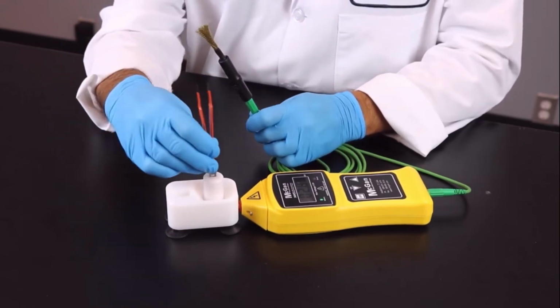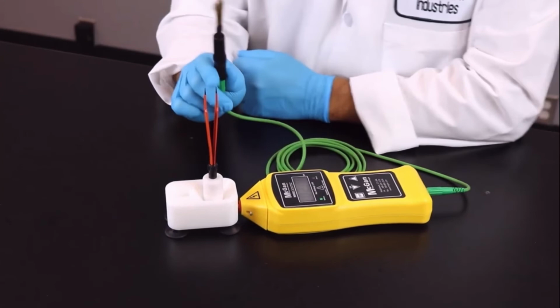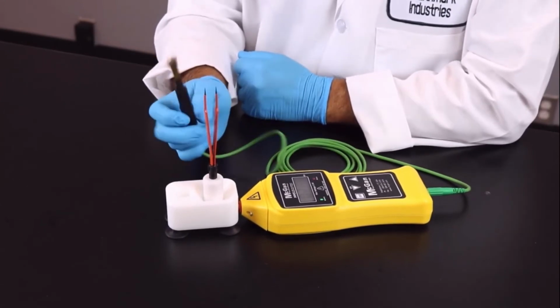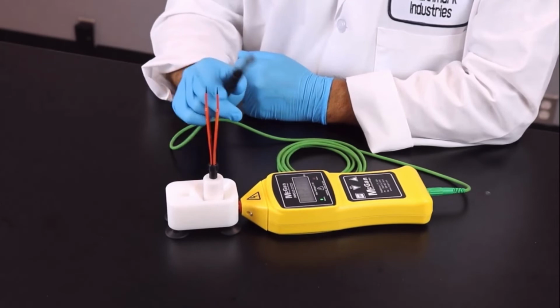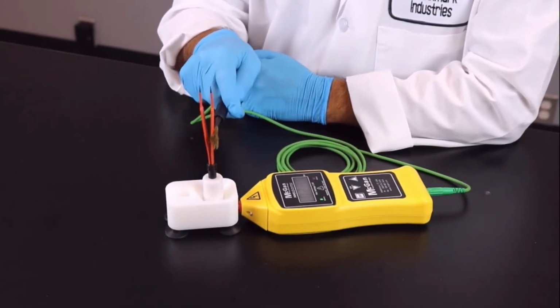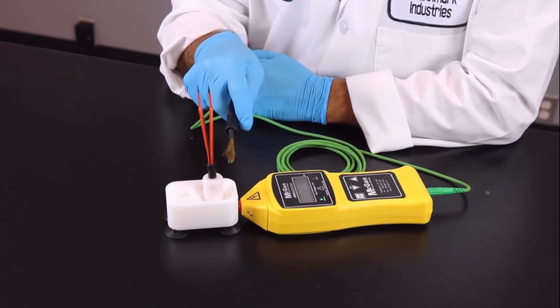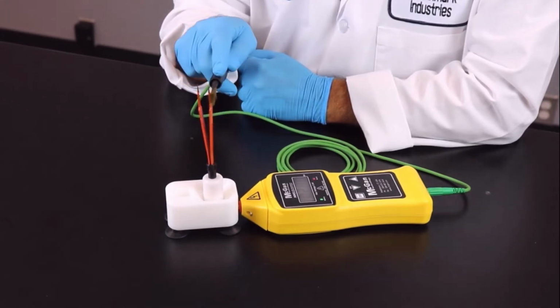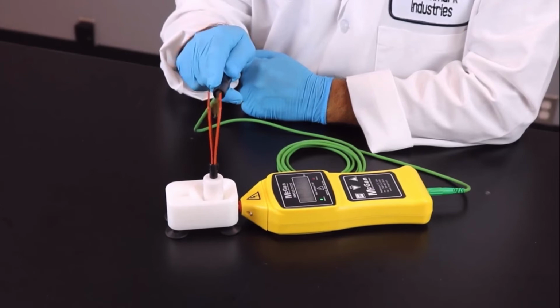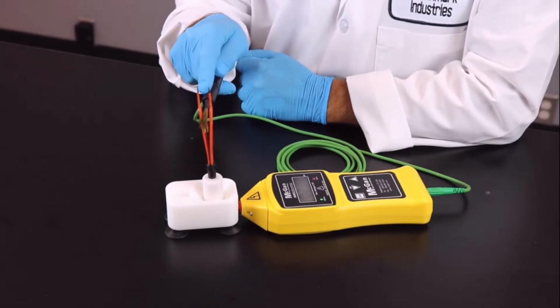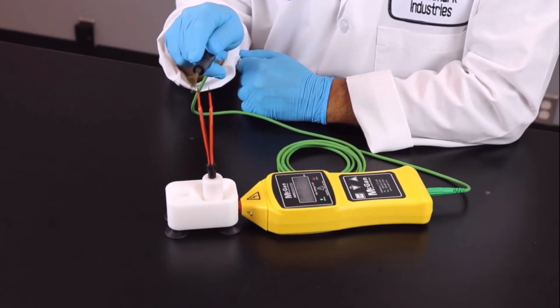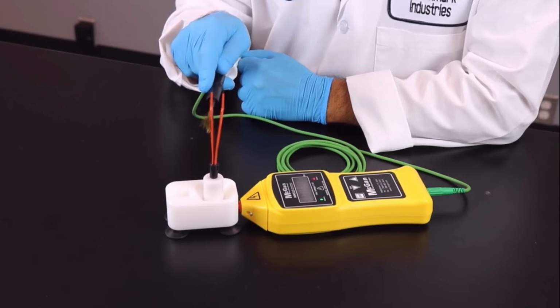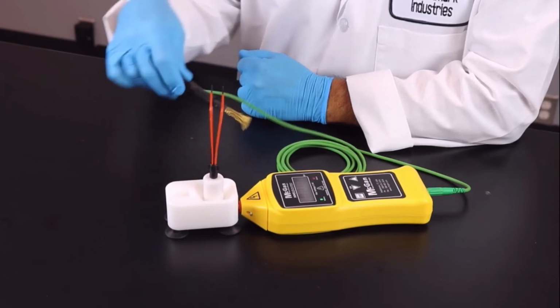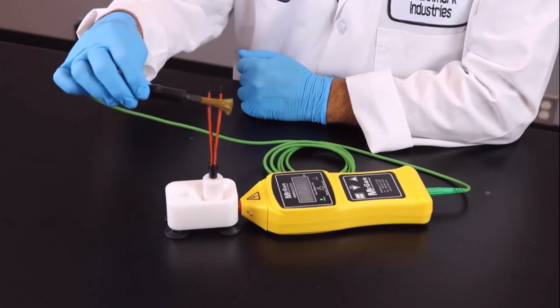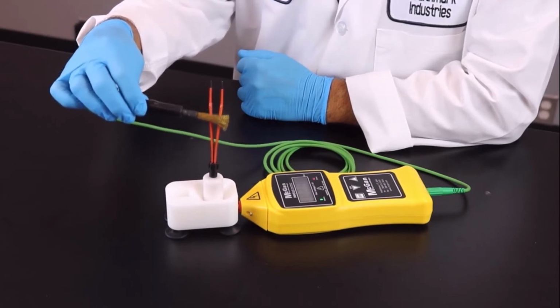Then you're going to take your bipolar insulated forceps and you want to make sure that it's grounded. So you're going to go on the very top here, and the technique is you're going to make an M. You start at the base, you go up the shaft, and each shaft is called a tine. So on this side of the tine you're going to go up, that's normal because that's exposed, all the way down into the middle, up, and as you can hear and you can see there's a break, all the way up, which that's normal, all the way down, there's another break, which is damage, all the way down to the base.